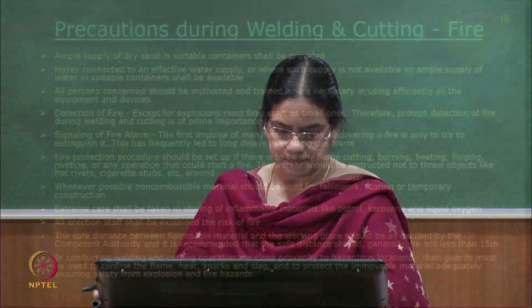Generally the fire starts small. If you put all your measures into putting off those small flames, then it does not spread. The minute the fire starts spreading, it becomes too much for you to control, because a spontaneous reaction starts happening. So, there should be a fire watch person allotted by the hot work permit system itself. During that system we should identify who the fire watch personnel are, and they should be looking for all these small fires or sparks spreading out of your welding operation, and try to put off all these small flames instantaneously before they spread into a very wide fire or explosion.